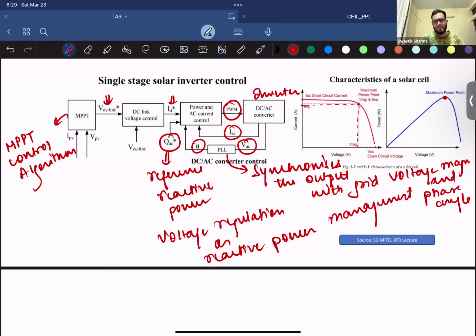I don't have a perfect explanation for this question, but as far as I can tell, the DC link voltage control that we provide is usually used to output the DC link in such a way that your maximum power point tracking is there. Usually your MPPT, you run your controller at MPPT only when it's connected to the grid. You don't want it to run at MPPT otherwise, because following the maximum power could be difficult, as the irradiance could switch its values very quickly.